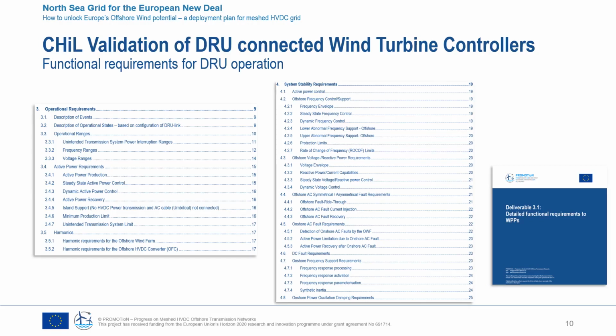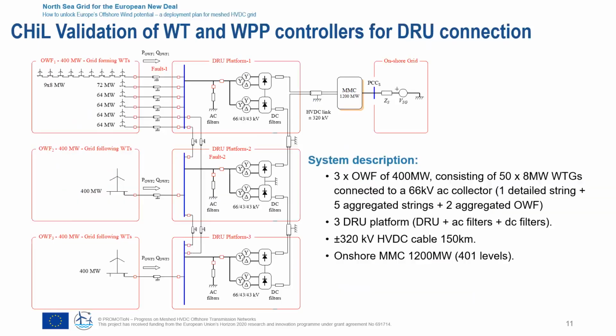First of all, we have to consider the functional requirements for DRU operation that were defined earlier in the project and that have been used also for the validation using offline simulations. Those requirements are very detailed and include both islanding operation and synchronized operation to the onshore HVAC grid. The system we have considered for the control hardware in the loop validation consists of 3 offshore wind farms of 400 megawatts each.